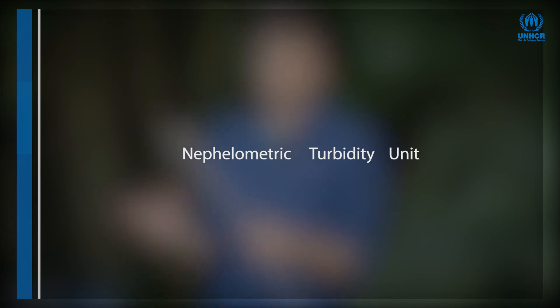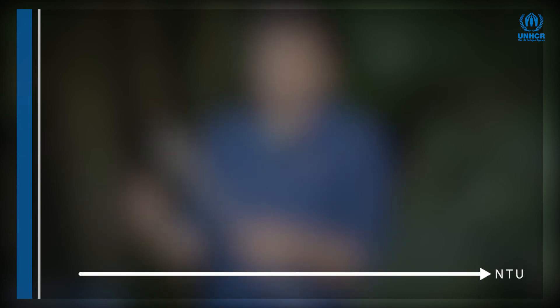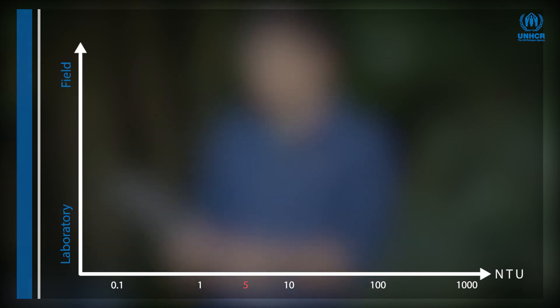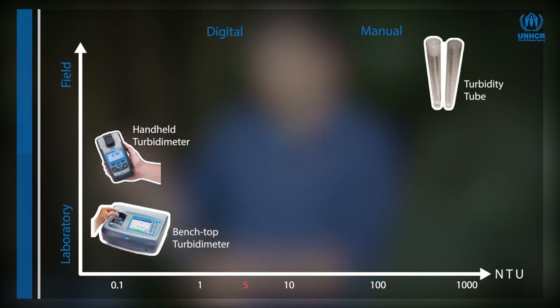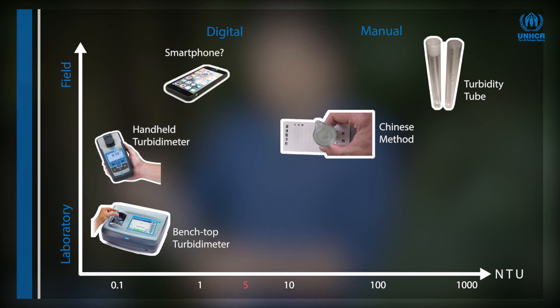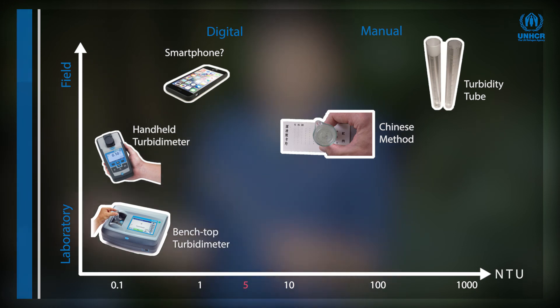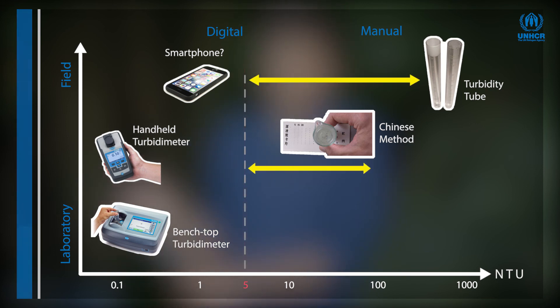Various units are used to express the degree of turbidity, however the most common is Nephelometric Turbidity Units, or NTU for short. Turbidity can be measured in many ways — depending on the purpose, it may be measured with digital meters with high precision or through manual measurement with lower precision. There are even smartphone applications, although this technology is relatively new and untested. For low-resource settings, manual measurements are most common, giving accuracy down to five NTUs. For greater precision, digital turbidity meters are needed.